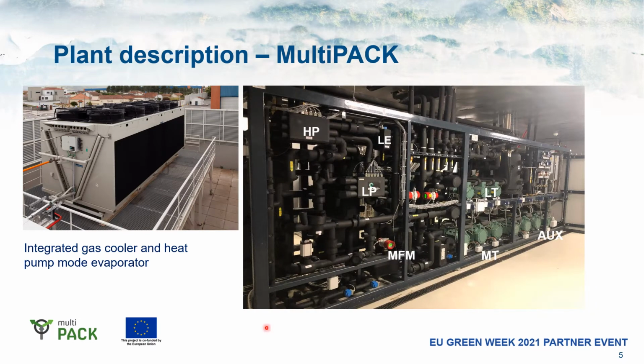If we take a look into the machine room, we see on the right side the MultiPACK. So we see the compressor stages for the low temperature evaporation, the medium temperature evaporation, and the auxiliary or intermediate temperature compressors. We see the mass flow meters which are installed in order to measure the mass flow rates in the pack. And we see the different ejector blocks as well as the high pressure expansion valve, which could be run in parallel. On the outside of the machine room an integrated gas cooler is placed, which, as I said on the previous slide, can also run as an evaporator in the heat pump mode.